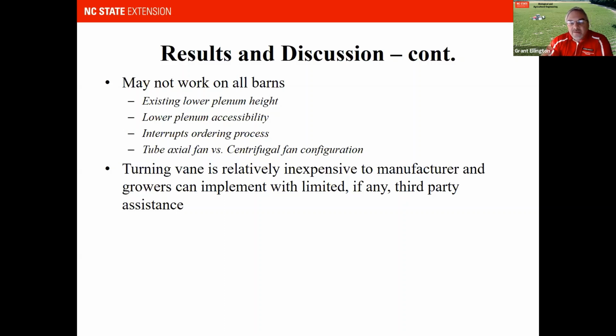Tube axial fan versus centrifugal fan configuration: most of the 10-box barn type barns use tube axial, or big prop, fan configurations. But barns with centrifugal fans already have the fan housing geometry delivering air into the lower air plenum at a 90-degree angle, so the turning vane may not work as well in a barn with a centrifugal fan.